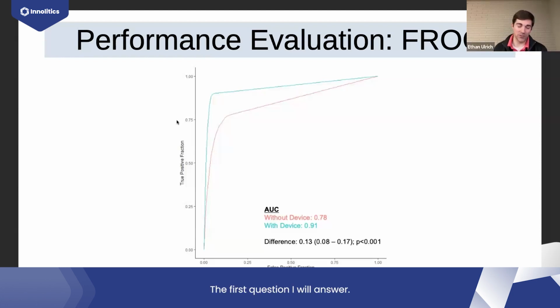Yeah, the first question I will answer, no, the FDA probably will not give you a recommendation for how many you should use. They really rely on the sponsor to justify how many cases they're going to use. Yes, for the situation where you have multiple things that you're detecting, I would definitely reach out to a biostatistician to determine how many cases you might need to do that. It just adds another level of complexity.